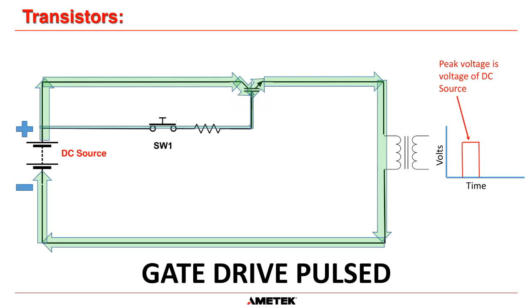But when we send a short signal, when we push this button momentarily, the IGBT turns on momentarily, and what we'll get is this square wave, which will be at the voltage of the DC source. So if this is 135 volts DC, which most stationary plant batteries are, then the peak of this voltage will be 135 volts DC too.